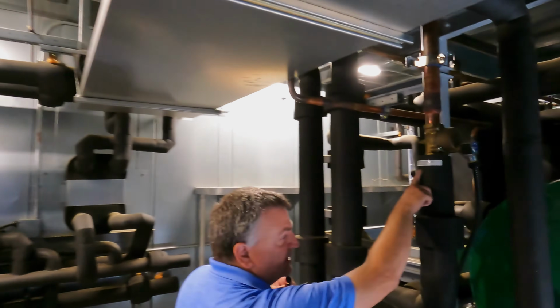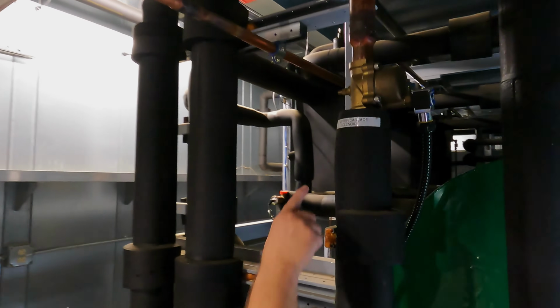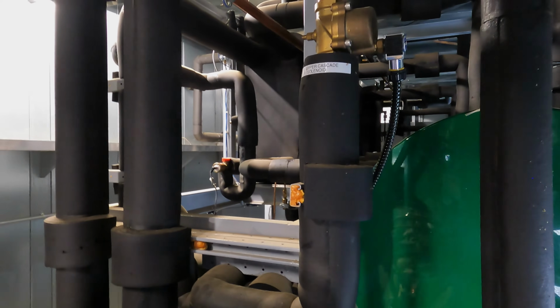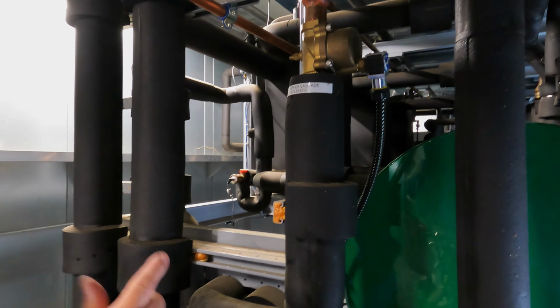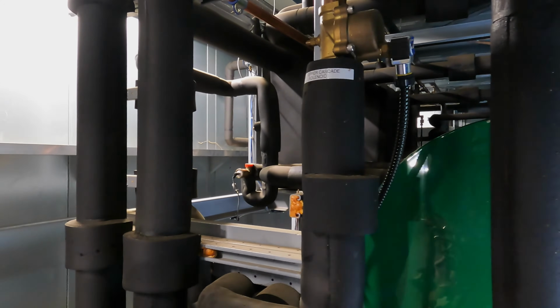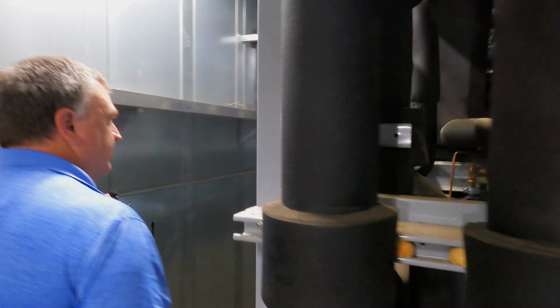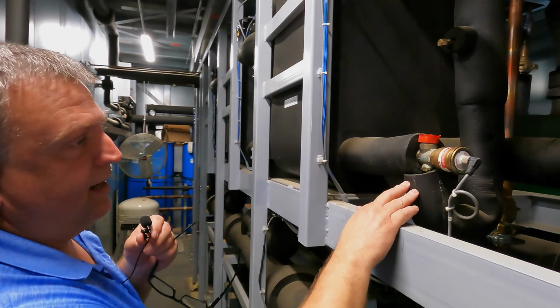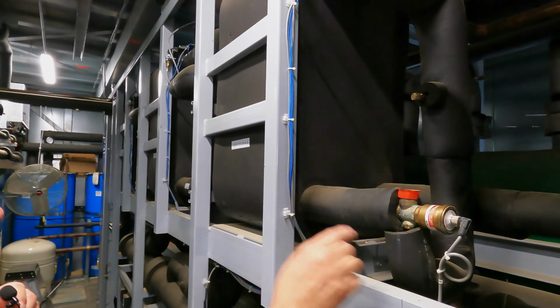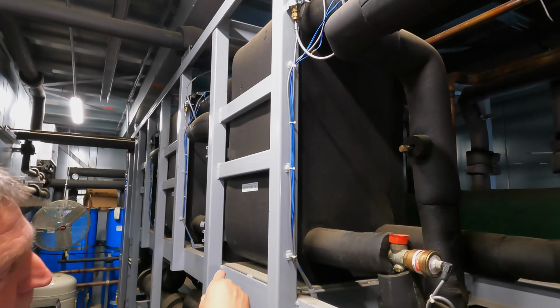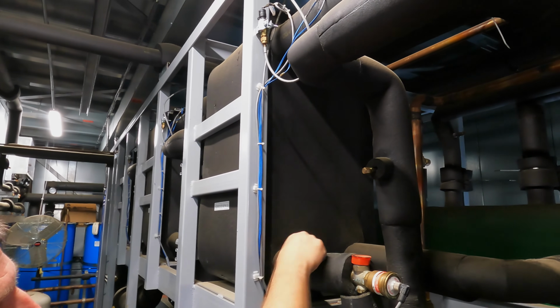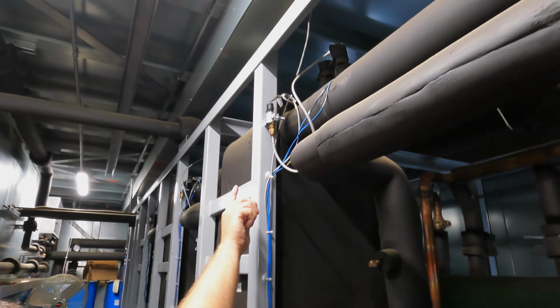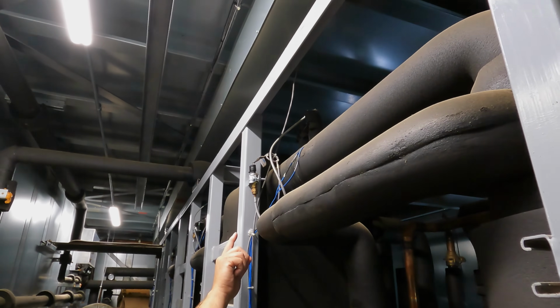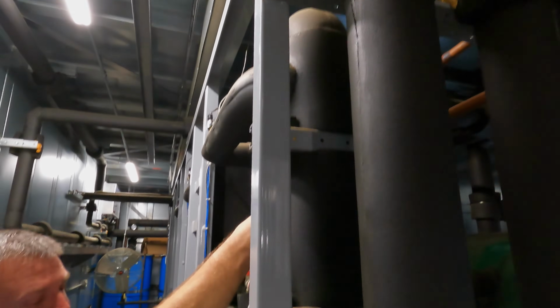It comes over, and it comes to our upper Cascade solenoid. If this is not energized, nothing works. This one thing has to be energized for the system to work. If it's not energized, we are not feeding liquid to our condenser evaporator, which is right here. So we go in as a liquid, we've condensed our CO2, and now we're in an evaporated vapor state coming out. Now this is our suction line, suction header.